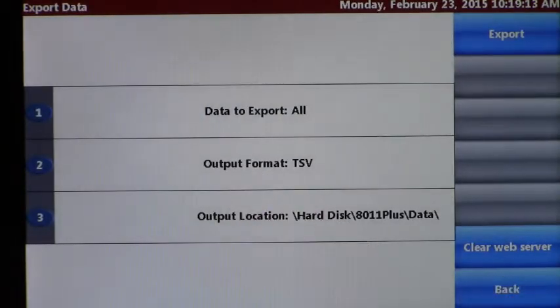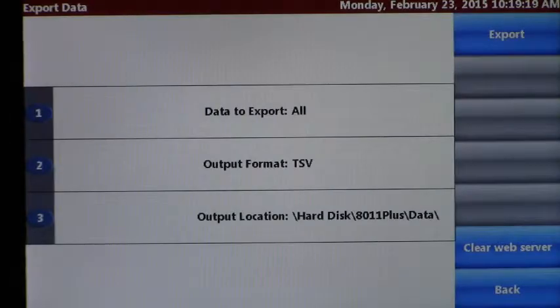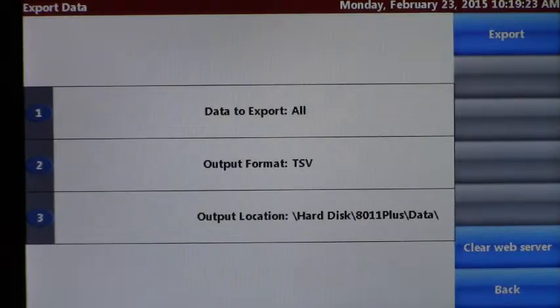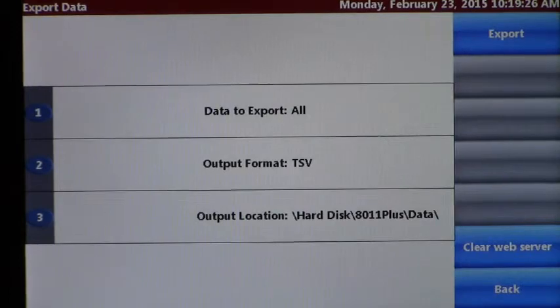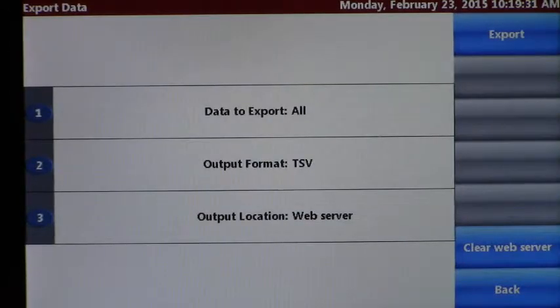Option two is the output format. We've got TSV option or PDF. Option three is where we're going to locate the data. Either we're going to send it out to the USB or we're going to send it to the web server. We're setting up the web server so we'll select option one.